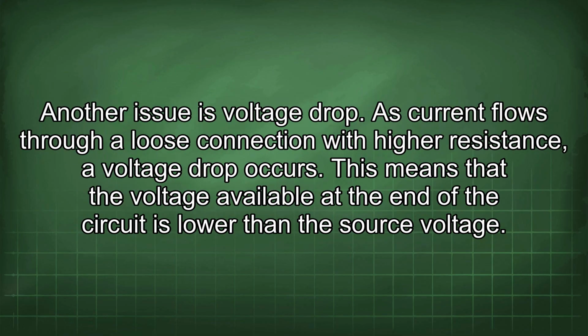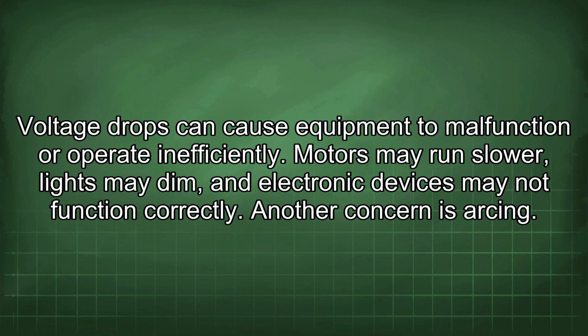Another issue is voltage drop. As current flows through a loose connection with higher resistance, a voltage drop occurs. This means that the voltage available at the end of the circuit is lower than the source voltage. Voltage drops can cause equipment to malfunction or operate inefficiently. Motors may run slower, lights may dim, and electronic devices may not function correctly.